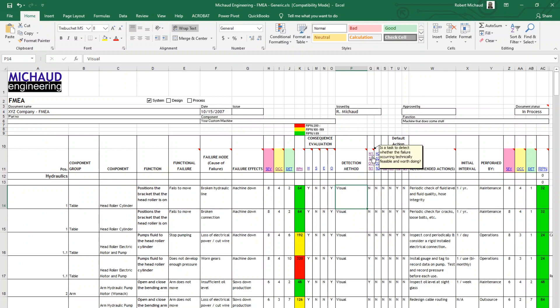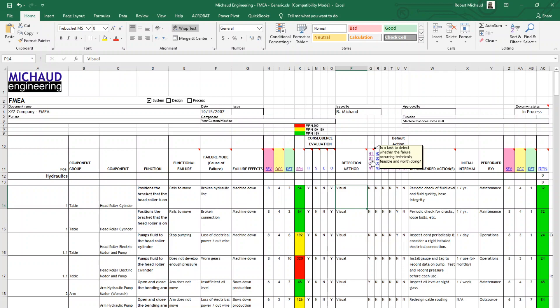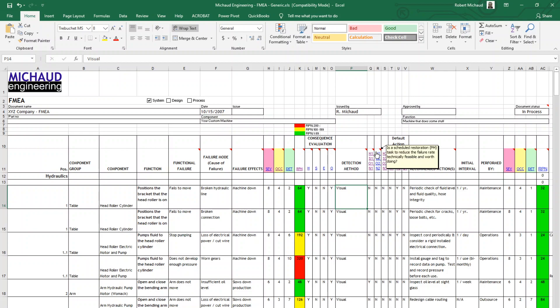And then we're going to look at these criteria for grading the next several questions. Is a task to detect whether the failure is occurring technically feasible and worth doing? This is an important question because it may be that a specific failure mode or the ability to detect a failure mode is not technically feasible or worth doing. If it is a component that's buried deep within the machine, it may not be feasible to do that. Likewise, is a scheduled restoration or PM task to reduce the failure rate technically feasible and worth doing? In other words, if we were to schedule a PM to go in and service, for instance, a hidden belt periodically, would that make a difference? Yes or no.